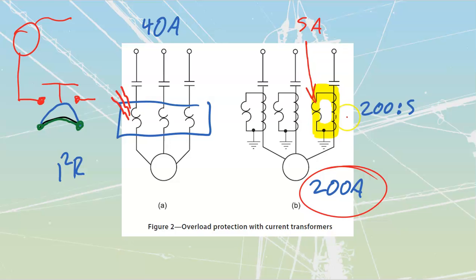It is really no different than if I had a dedicated apprentice that was just standing over here with a clamp-on ammeter. Okay, that's you with a clamp-on ammeter just watching this the whole time. You wouldn't get distracted. You'd be able to go and watch that clamp-on ammeter the whole day, right? And you would have your hand on a push button that you could go and shut it off. That's all that the overloads are doing, is they're monitoring the current, and if the current gets out of control, whack, we just take that system right out.